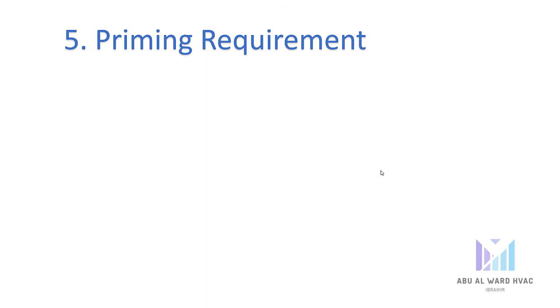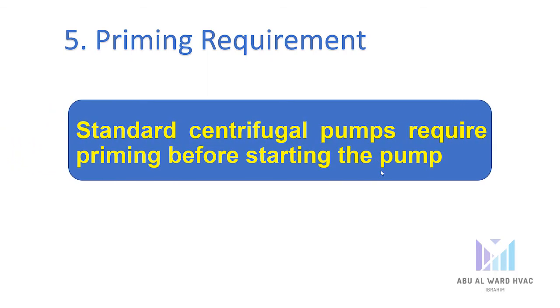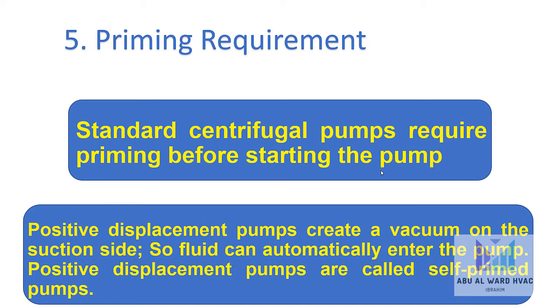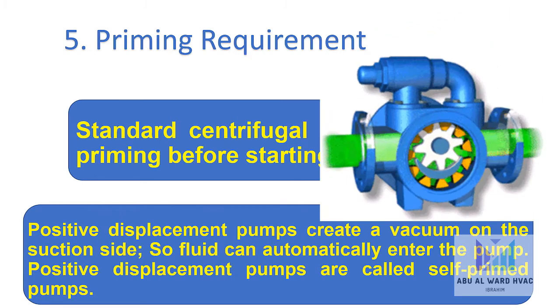The fifth aspect is priming requirement. Standard centrifugal pumps require priming before starting. Positive displacement pumps create a vacuum on the suction side so fluid can automatically enter the pump — positive displacement pumps are therefore called self-priming pumps. Due to the presence of entrained gases, centrifugal pumps are more susceptible to cavitation compared to positive displacement pumps.